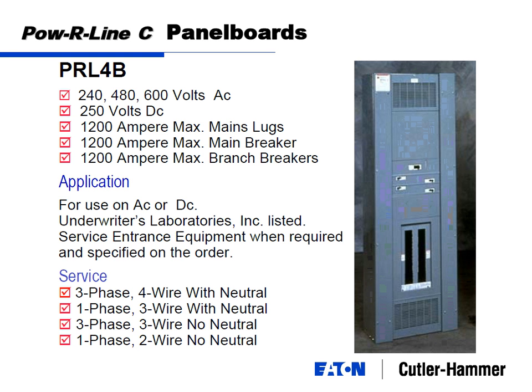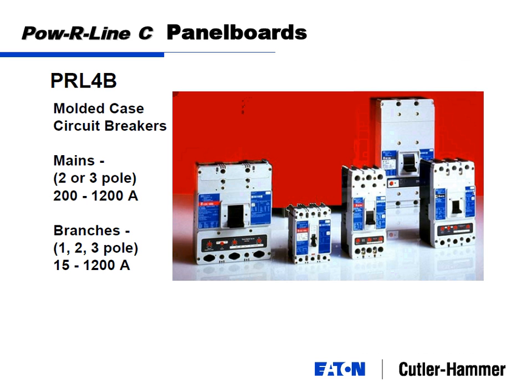And notice in this picture, they actually have a smaller chassis as well. So they've got Powerline 1 breakers in here as well as power distribution feeder breakers. And here's what the family looks like up through 1200 amp. Basically, these are all molded case circuit breakers. This is a molded case circuit breaker, but it could also be called a miniature circuit breaker or some other names. But when we talk molded case circuit breakers, this is often what people envision, the larger breaker.